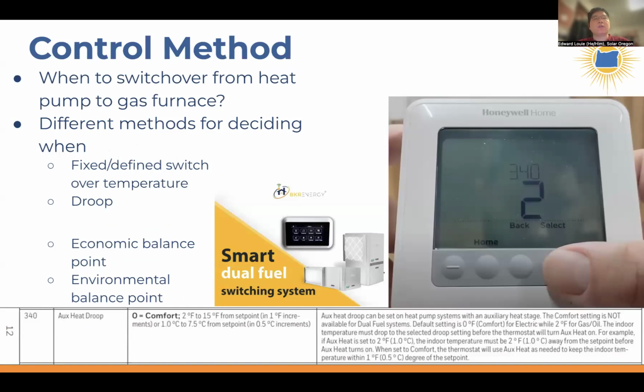Now, let's get into control methods. If you have a system that has the option to heat with gas versus heat with electricity via heat pump, then the thermostat needs to decide when to switch from one to the other. The first two bullets are the common ways that this switching occurs. One is to just define a fixed temperature to switch over. That's not a very good method because let's say on calculation the heat pump can keep up to like 20 degrees outside, but there are different 20 degrees outside. It could be 20 degrees and 20 miles per hour blowing wind, or it could be 20 degrees and sunny outside. Those two scenarios result in very different heat loads on your house. And so that's why a fixed temperature switchover is not very good.